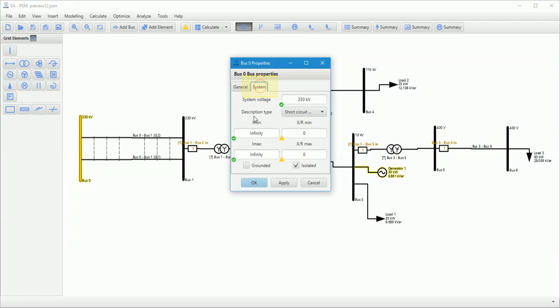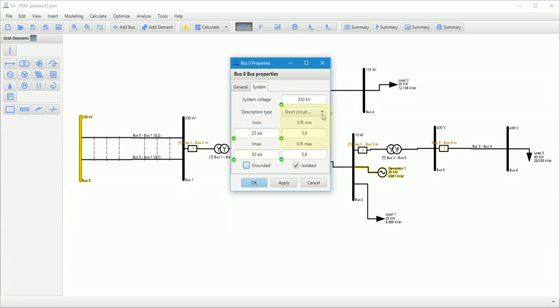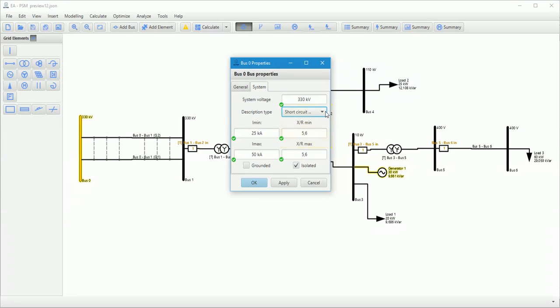In order to calculate short circuit parameters, user needs to enter system information provided by grid operator. This information consists of short circuit currents and impedance ratio for system bus. It is also possible to define system by short circuit power or system impedance. System can be grounded or isolated.